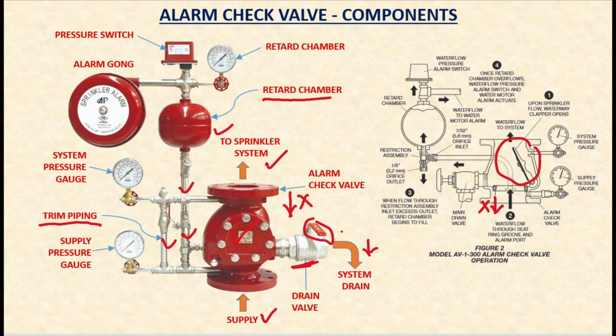Now the next part is the alarm gong, which is basically used to sound an alarm. This provides immediate audible notification of a fire event to those near the premises. An alarm gong is a mechanical device. When a sprinkler head is activated and water begins to flow through the system, the flow triggers the alarm check valve. First the check valve is triggered, which sends water through these small pipes to the retard chamber and to the alarm gong. So we can say now that the alarm check valve is designed to activate alarms when water starts flowing due to the activation of sprinkler heads. Okay, I hope you understand.